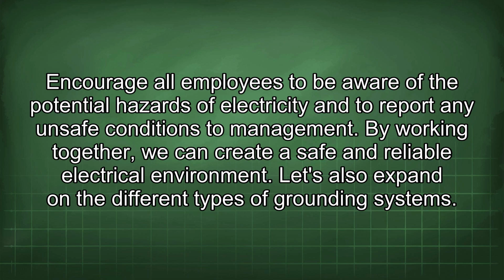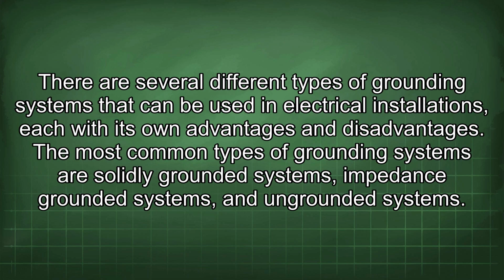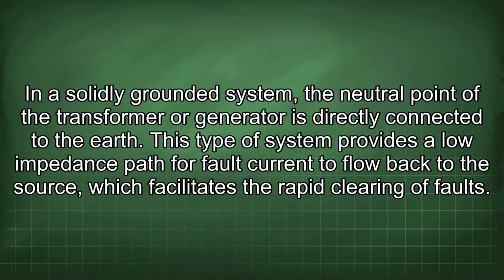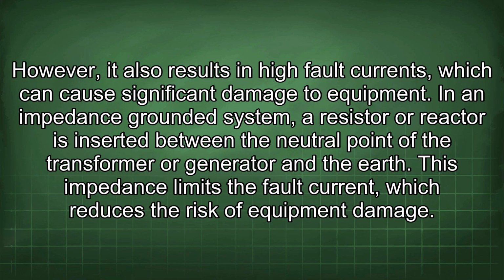Let's also expand on the different types of grounding systems. There are several different types of grounding systems that can be used in electrical installations, each with its own advantages and disadvantages. The most common types of grounding systems are solidly grounded systems, impedance grounded systems, and ungrounded systems. In a solidly grounded system, the neutral point of the transformer or generator is directly connected to the earth. This type of system provides a low impedance path for fault current to flow back to the source, which facilitates the rapid clearing of faults. However, it also results in high fault currents, which can cause significant damage to equipment.